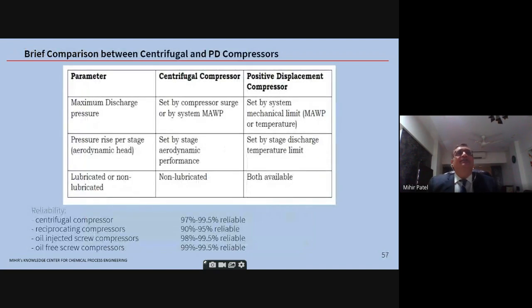Then a brief comparison between centrifugal and PD compressors. So this is a brief comparison of centrifugal and positive displacement. Important is the non-lubricated nature of the centrifugal compressor. In PD compressors, you can have both: lubricated as well as non-lubricated. Reliability is a very important parameter. Centrifugal gives the most reliability amongst all. Okay, and then the oil-free screw compressors at the bottom also give good reliability. These are used in instrument air and plant air services, and also in some polymerizable gas services.